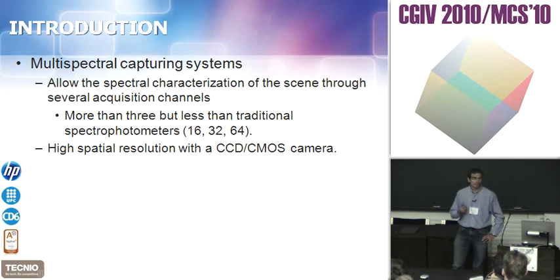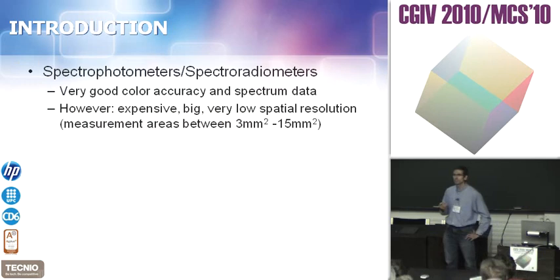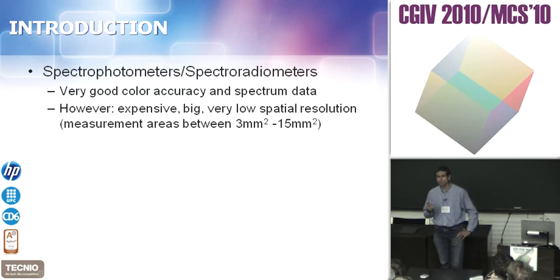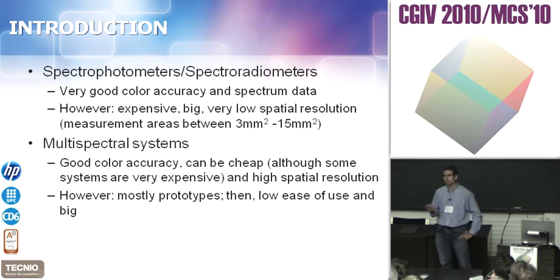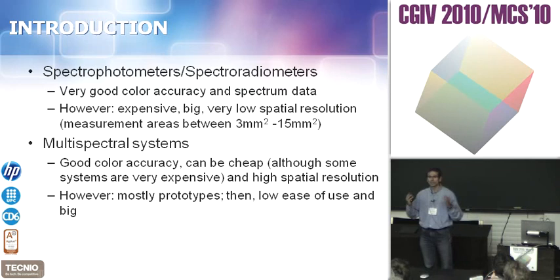Multispectral systems have the good advantage of very high spatial resolution using a CCD or CMOS camera. Spectrophotometers are distinguished by very good color accuracy and very good spectral resolution, but they only measure one point. In multispectral systems you can also get very good color accuracy, and you add the value of being able to capture a whole image with very high spatial resolution.